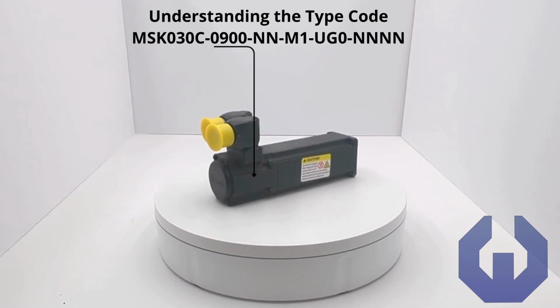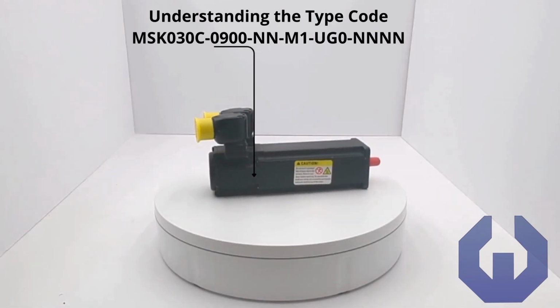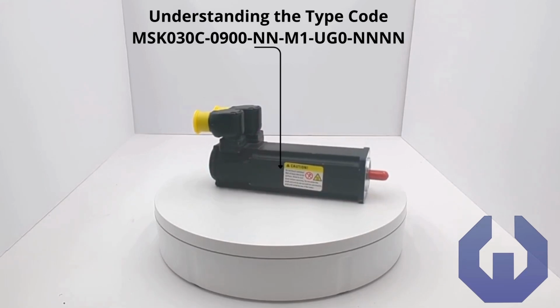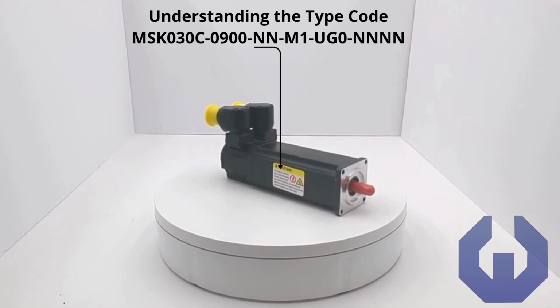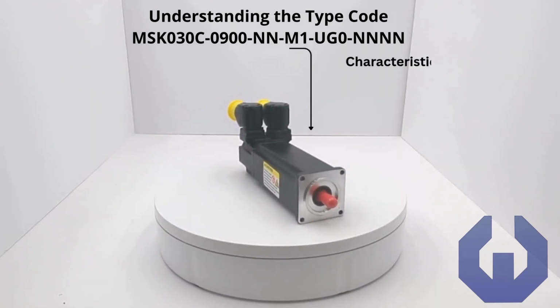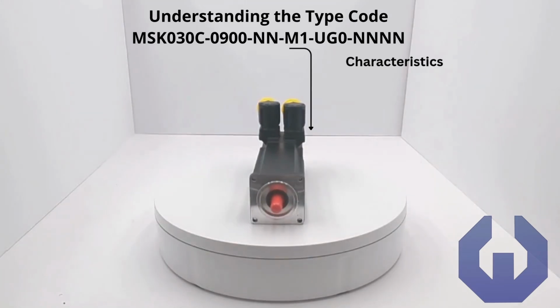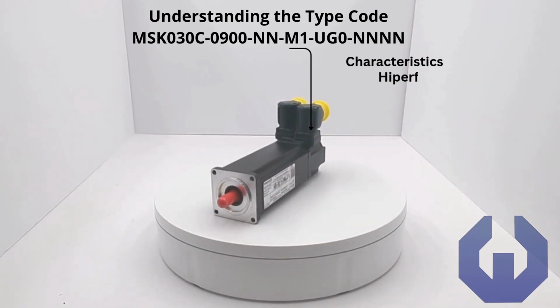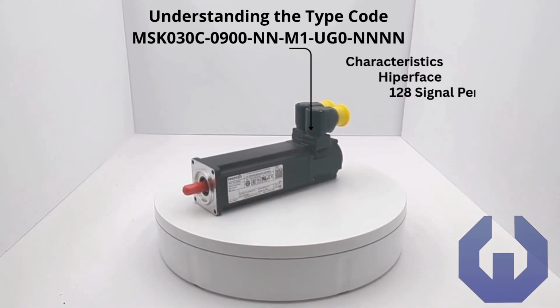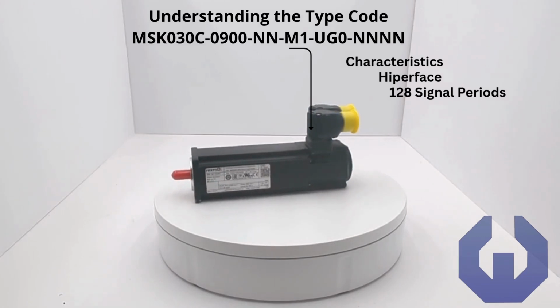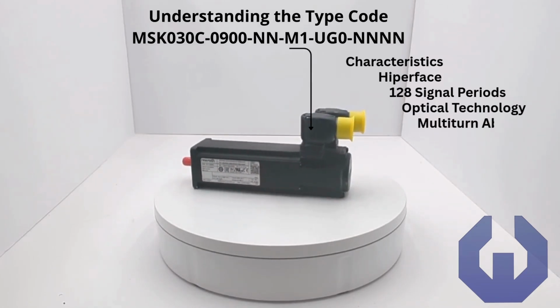0900 denotes the winding code for the motor is 0900. NN denotes the motor relies on natural convection for cooling. M1 denotes several characteristics about the MSK encoder.